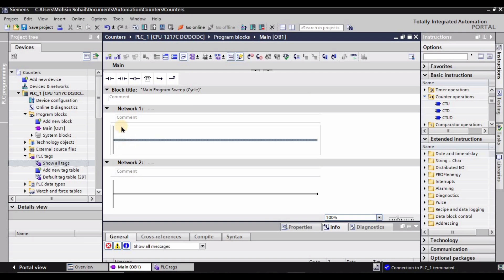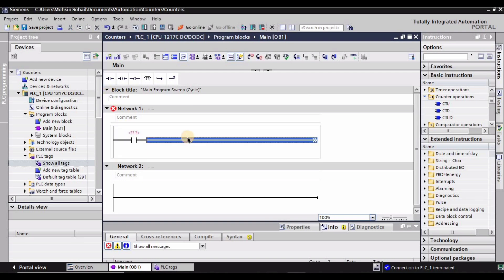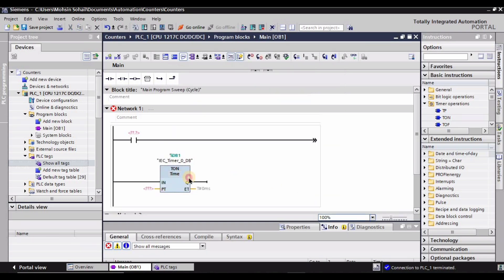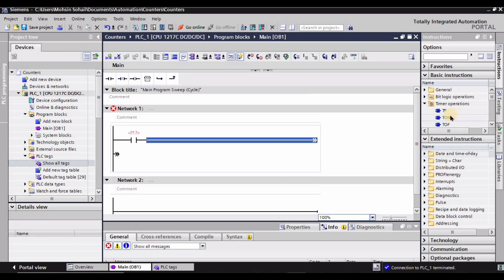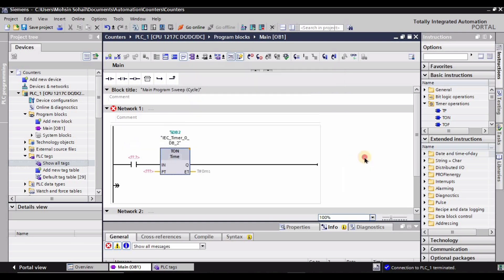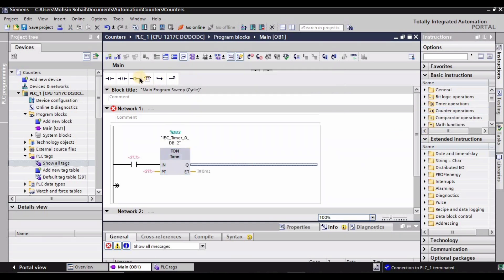Now let's move into the TIA Portal software to solve this problem. I will be using a normally open contact to give the input pulse. Under timers, I'm going to use a TON timer — that is timer on-delay. I had placed it at the wrong place so I deleted it, selected the correct line, double-tapped the TON timer, and clicked OK. Now we have the TON timer placed after the start push button.